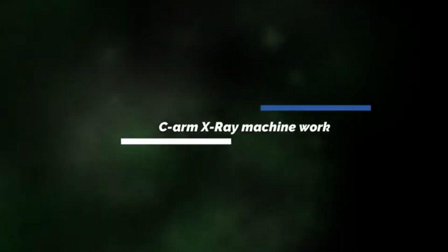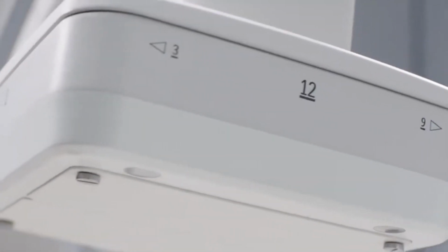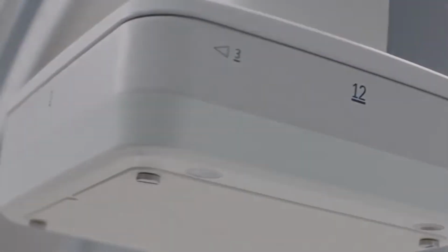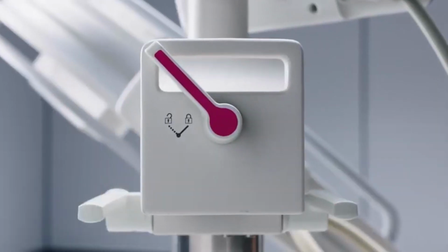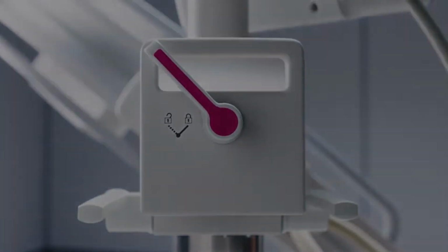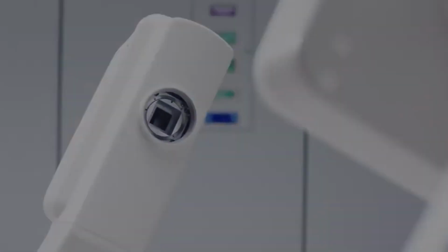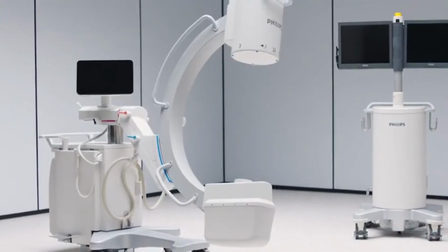Let's know how a C-arm X-ray machine works. A mobile fluoroscopic system, also known as a portable or mobile C-arm, comprises a generator, X-ray source, and an image intensifier or flat panel detector.